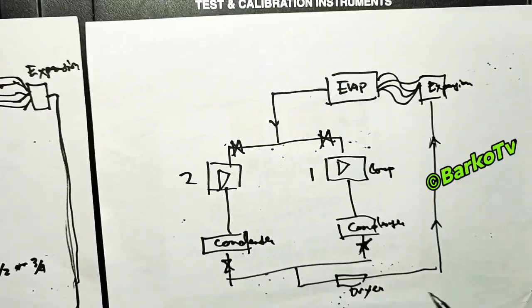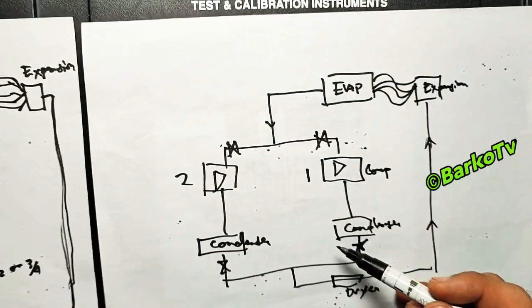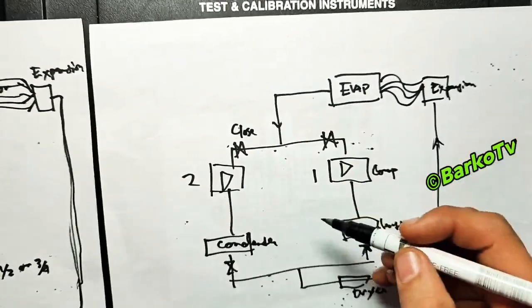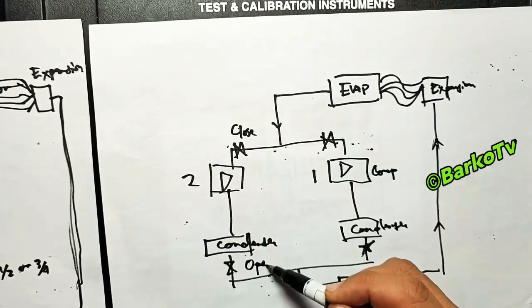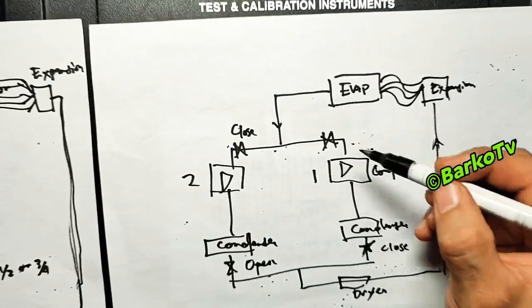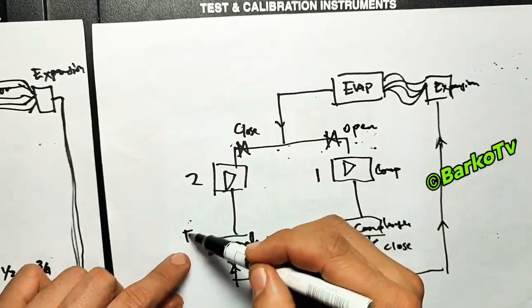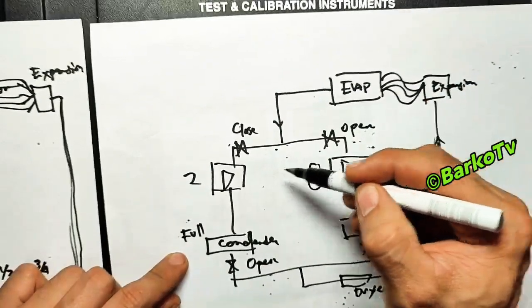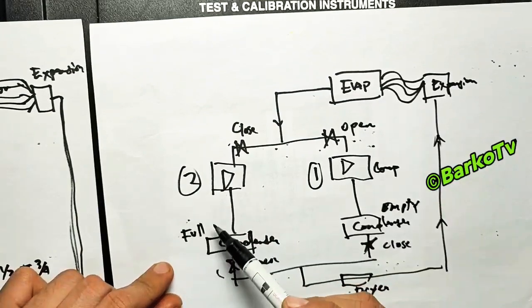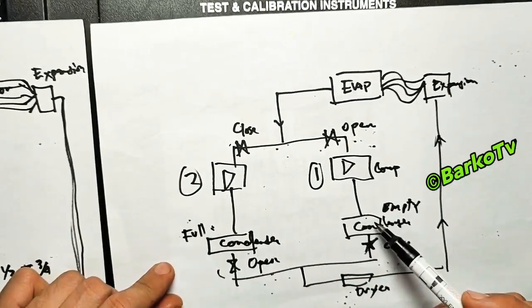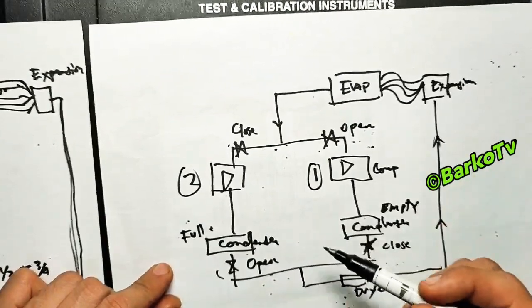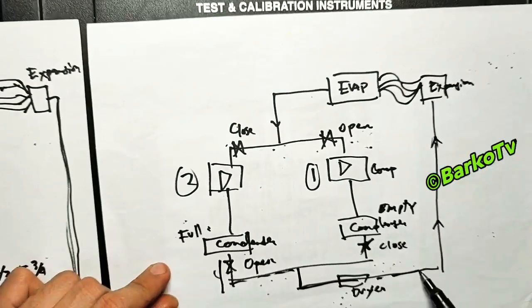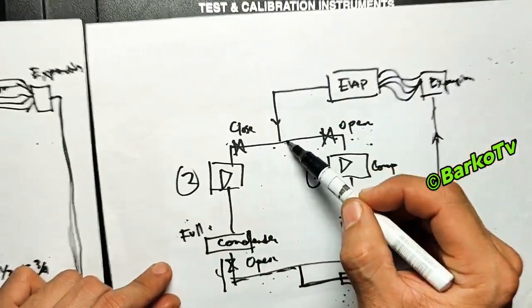At the dryer there is a charging valve for the liquid line. First step: close the suction for number 2. For the compressor, close it. Open after condenser for number 2, close number 1 condenser, open after condenser, and open suction for number 1. Number 2 side glass is about three fourths and number 1 is empty.